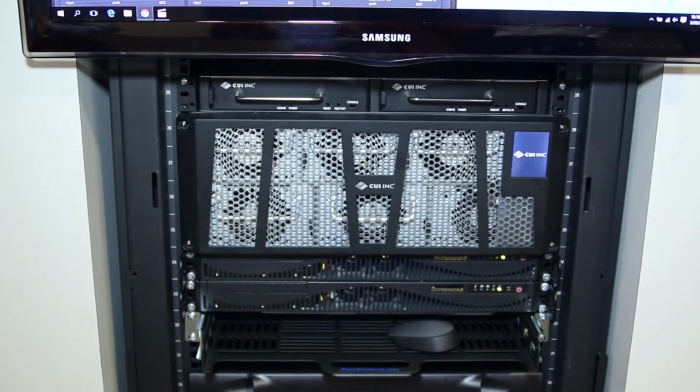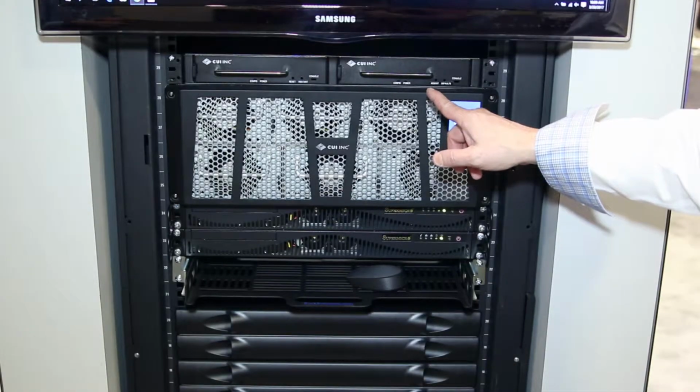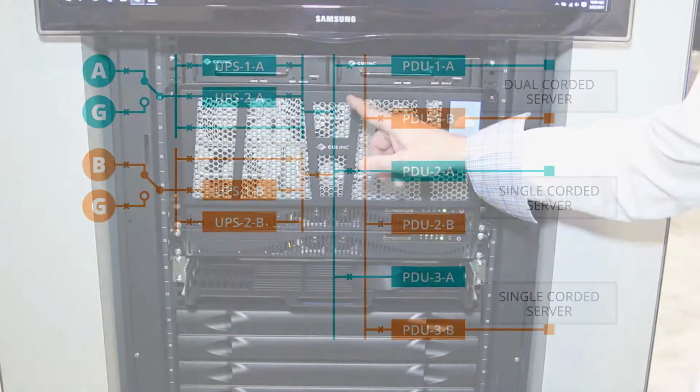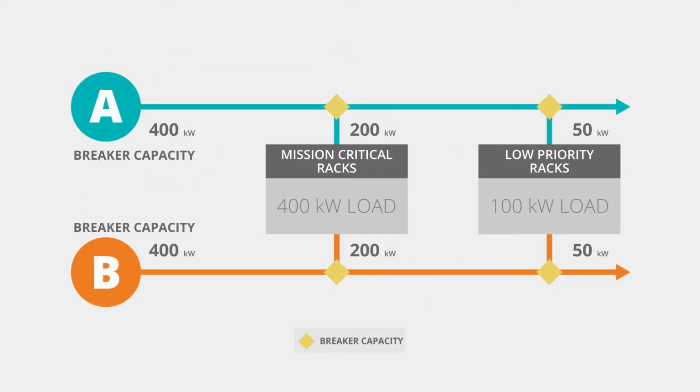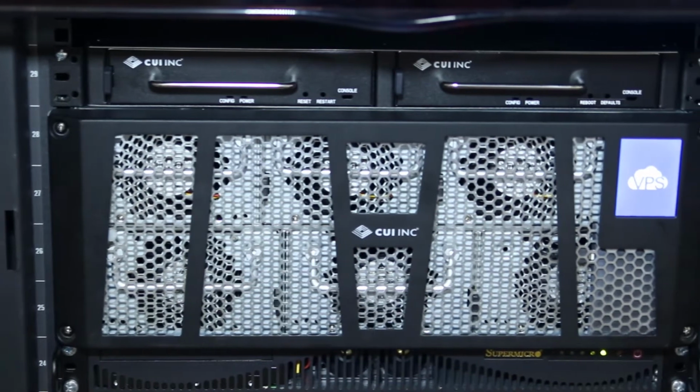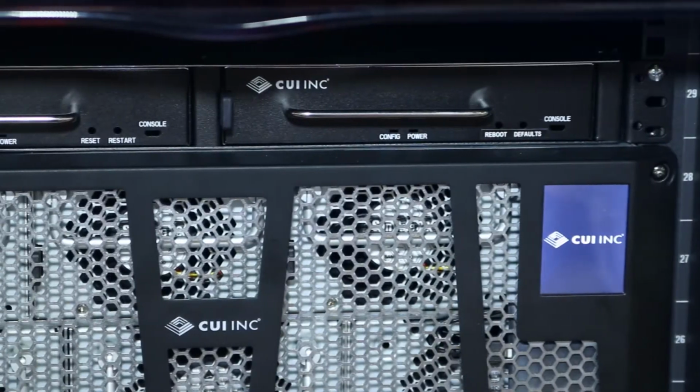The theory of the ICE switch is that you have an A feed and a B feed that come into the data center. Everything works off of A, and when A fails, everything switches to B. B is an untapped source. It's sitting there in case. There is a substantial amount of applications in a data center that's an N, so it doesn't need the 2N application. Wouldn't it be great if you could take that N and move it to the B? That's what this does. This allows those N applications to work off of the B feed, and in the event that the A feed goes down, it shuts everything off in a priority level on the B, and everything on A moves over. So if it's 20% of the N that used to be on the A, now you have 20% more that you can take advantage of with 2N applications.